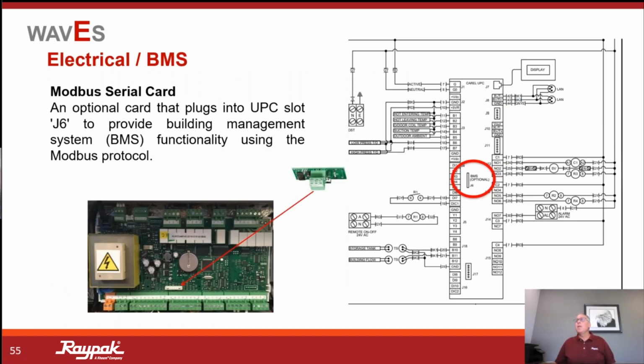Modbus is something we can do. In the appliance, we have a port here where, if you order the optional Modbus card, it's going to plug into this J6 terminal. We'll spend quite a bit of time in that Level 3 presentation for startup and commissioning. We'll talk about Modbus and all the different aspects, programmability that we have available to us. But from an installation standpoint, if you order the optional Modbus or BMS card, this is where it's going to plug in.